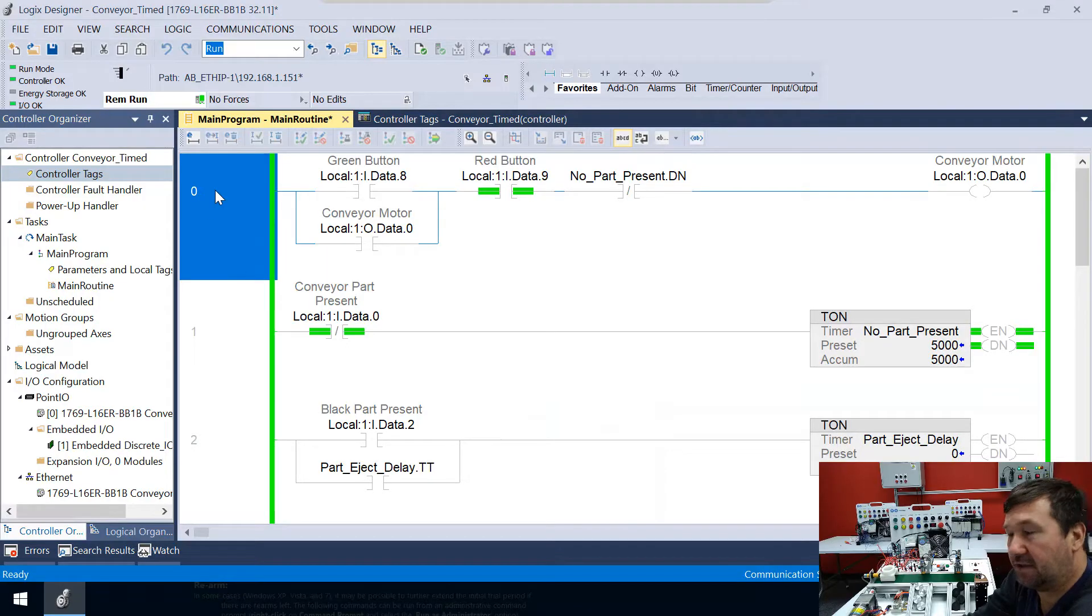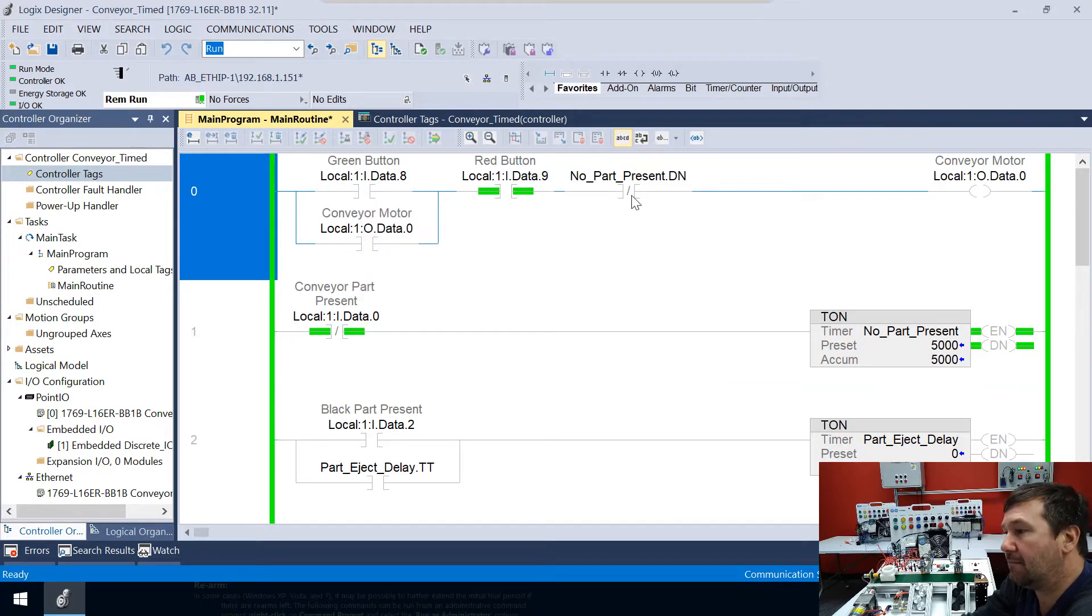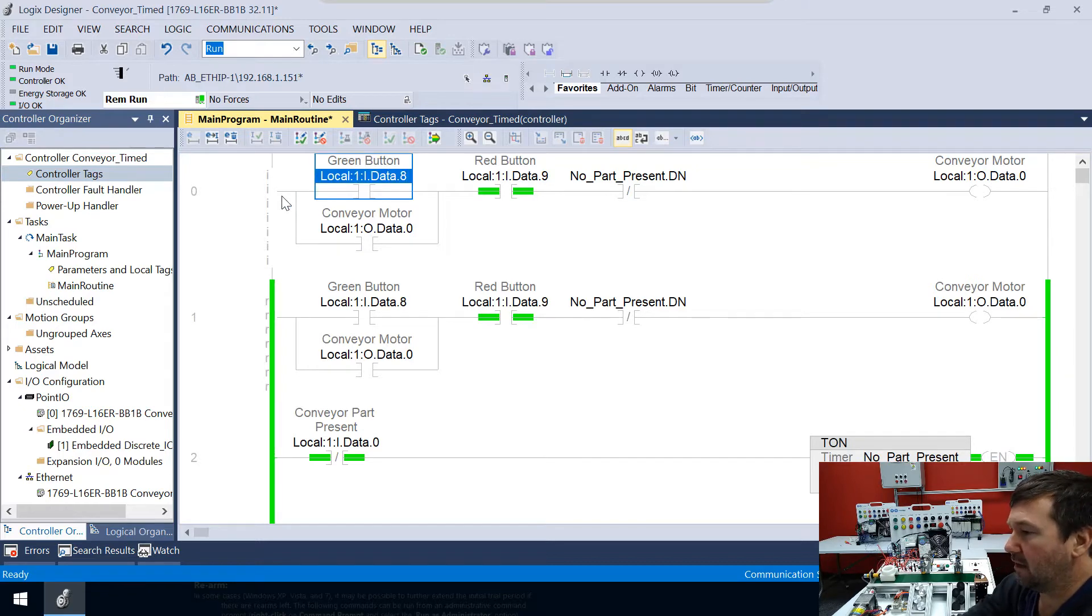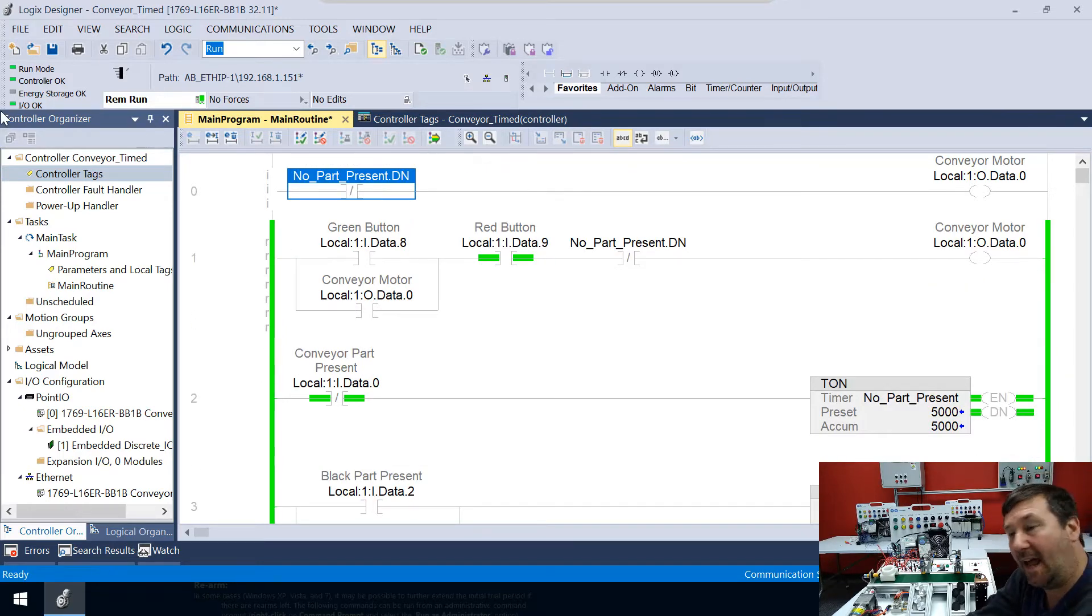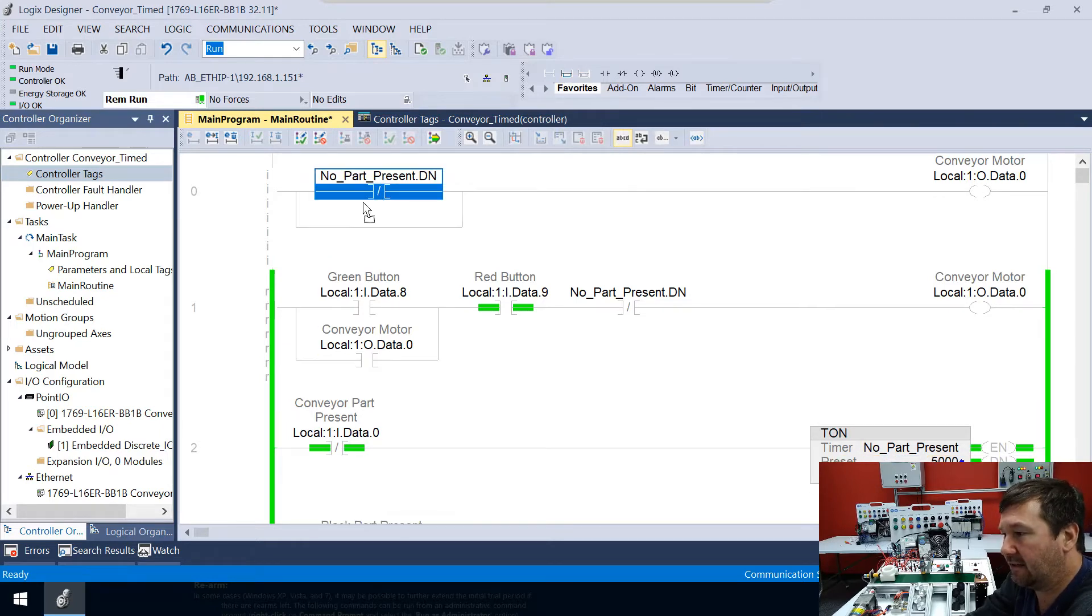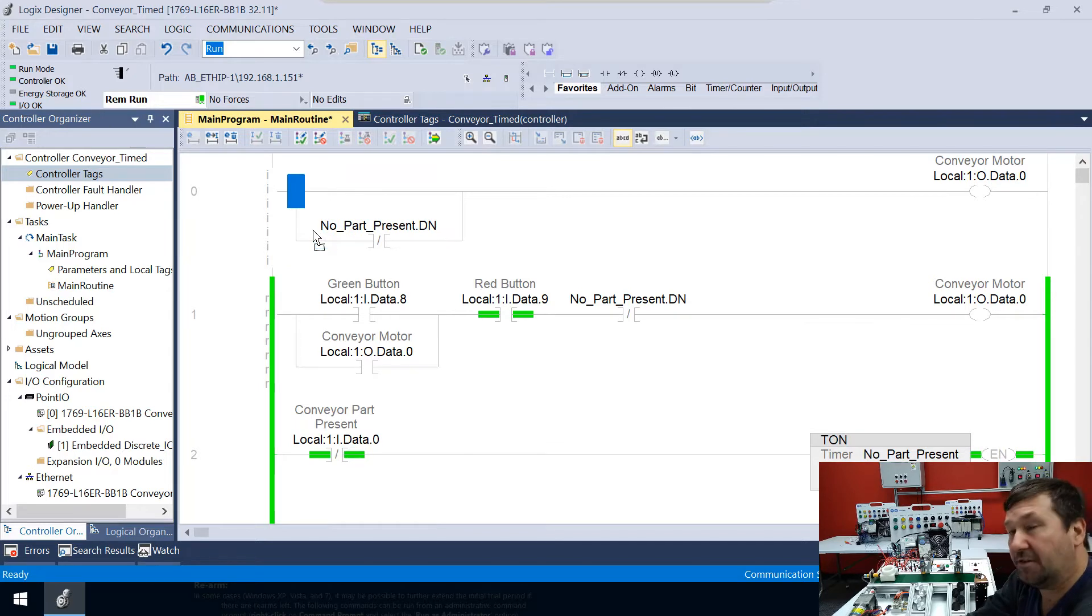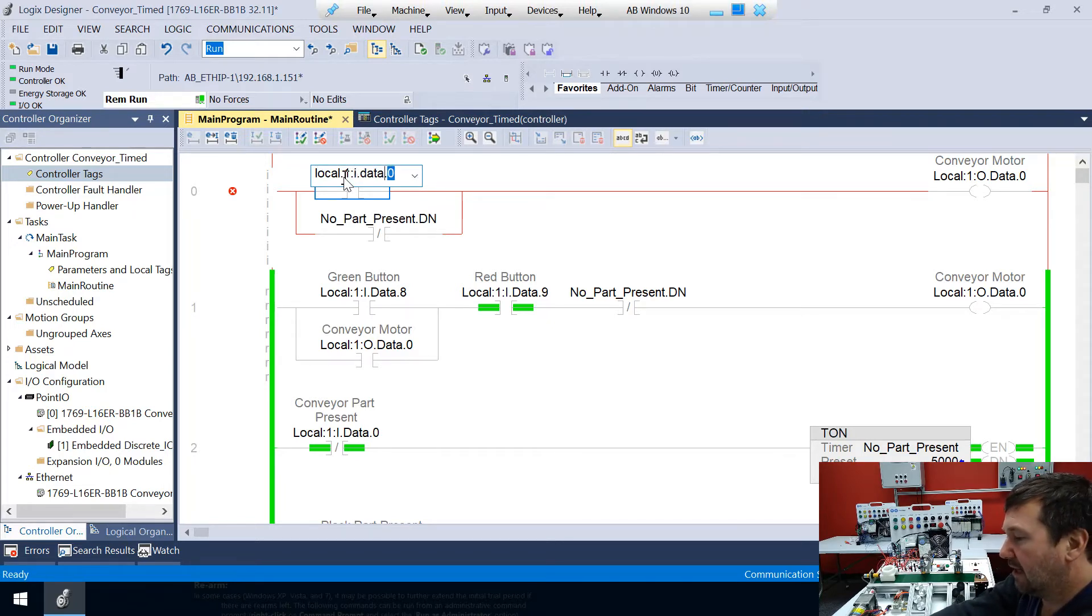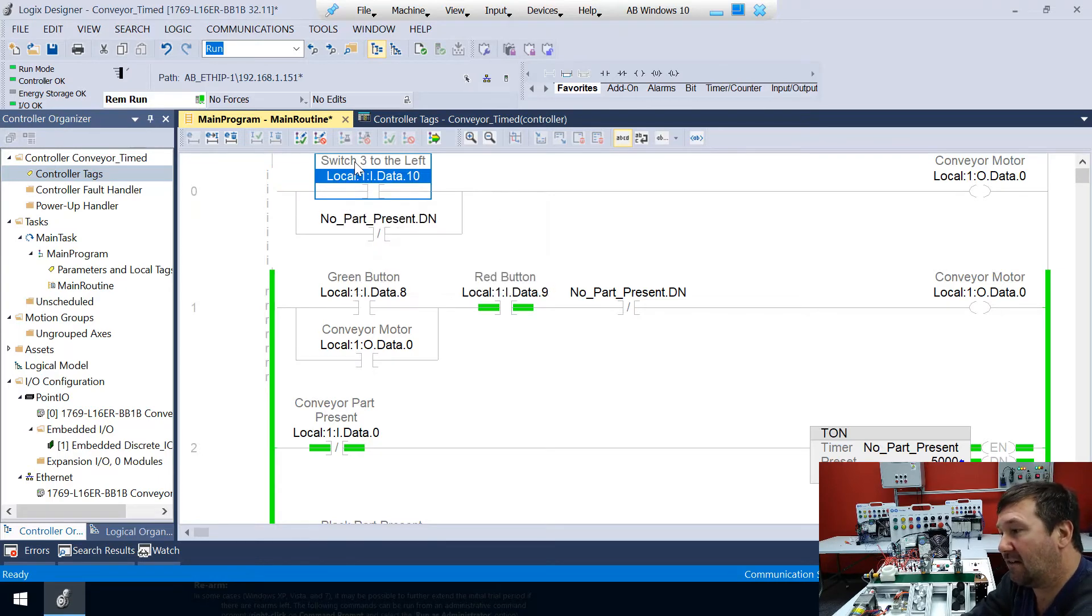So what we're going to do is we're going to edit rung zero, which has that conveyor motor in it. And we're only going to keep this part not present done for now. So what we're going to do then is let's just start off fresh. Let's delete everything but it out. And let's start by adding a branch and then drag the part present into the lower part of the branch. And so now in the top part of my branch, I'm going to put Local:1:I.Data.10. So that right now is labeled switch three to the left. Let's relabel it to switch three in hand.